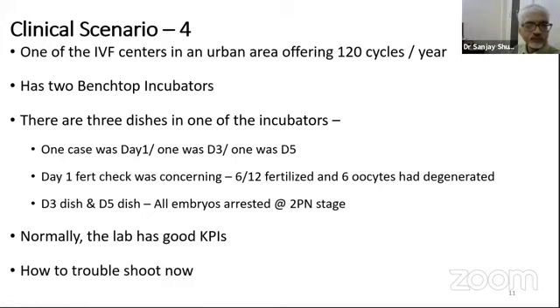So in this scenario, one of the IVF centers in an urban area offering around 120 cycles per year has 2 benchtop incubators. There are 3 dishes in one of the incubators. One case was day 1, one was day 3, and one was day 5. Day 1 fertilization check was concerning: 6 out of 12 fertilized and 6 oocytes had degenerated. Day 3 dish and day 5 dish, all embryos arrested at 2 pronuclear stage. Normally, the lab has good KPIs, but in this particular scenario, how would you troubleshoot now?